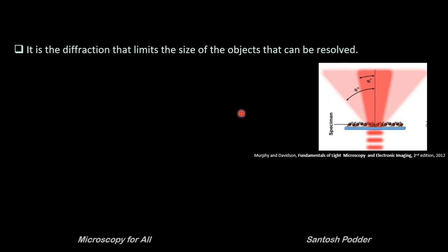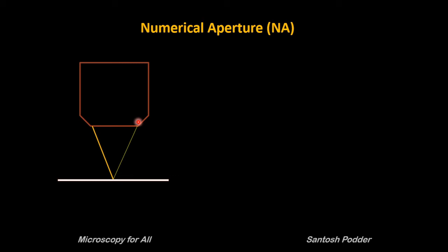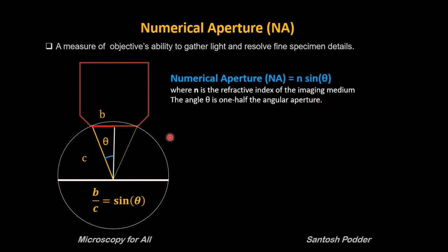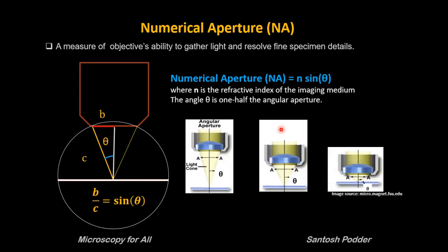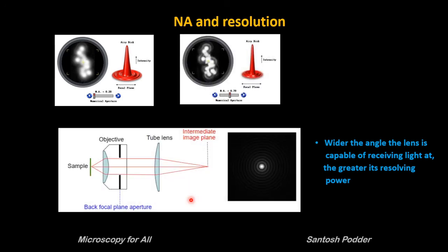So larger the number of diffraction orders collected by the objective, sharper and better are the details in the image. From here the concept of numerical aperture comes. Numerical aperture is the measure of an objective's ability to gather light and resolve fine specimen details. Numerical aperture is given by the formula NA = n × sin(θ), where n is the refractive index of the imaging medium and θ is the half angular aperture of the objective. Higher the NA, more the light-collecting capability, but remember: higher the NA, lower the working distance. Higher the numerical aperture, better the light-gathering capability and better the resolution.